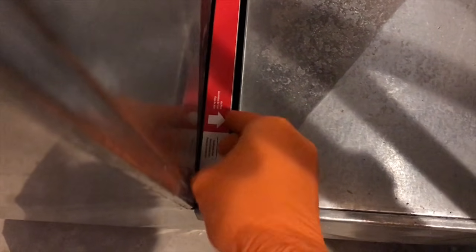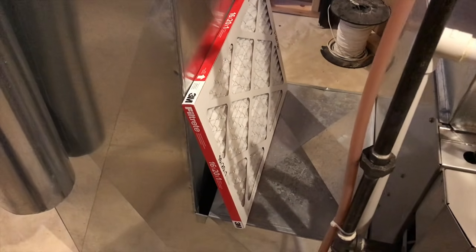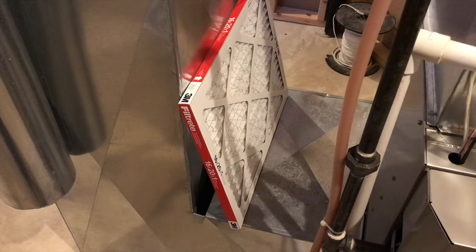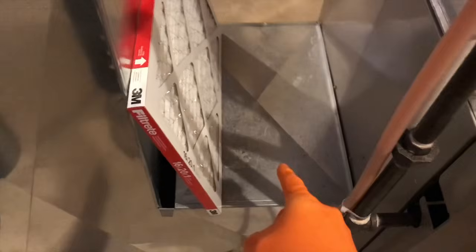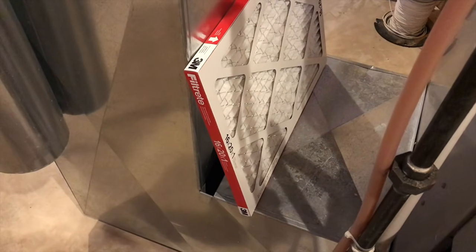If it is, go ahead and take your furnace filter out, and you want to check and make sure it is clean, because if it is not, that also degrades the airflow or ventilation to your actual furnace. And that's not good, because when you turn on your furnace, it goes through a 90-second test, meaning your fan motor and blade will spin for 90 seconds and run a self-test to ensure that it has proper airflow. And once it does, it sends the signal to the igniter, heats up, the burners kick on, and you have heat. However, during that 90 seconds, if it does not get proper ventilation, it's never going to turn on. So change your filter.